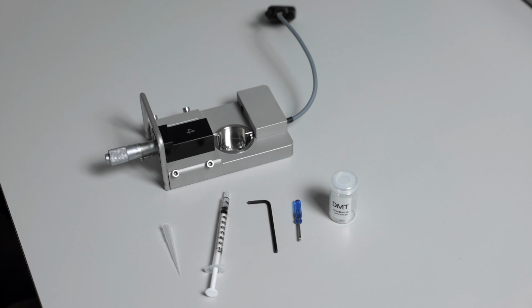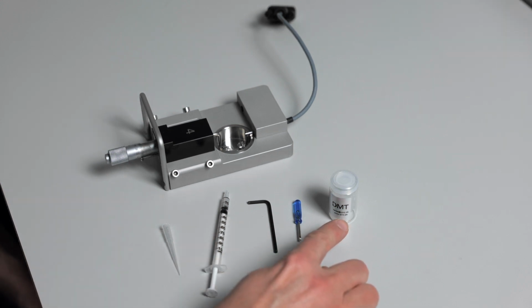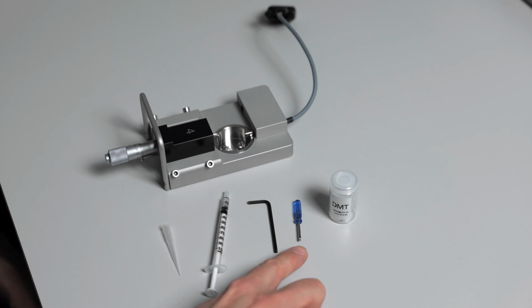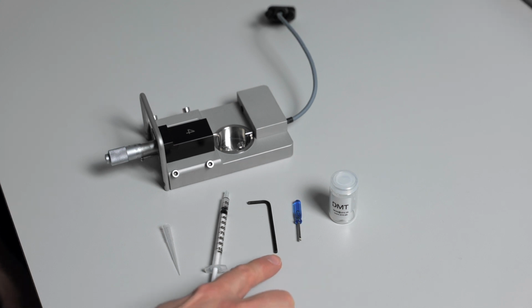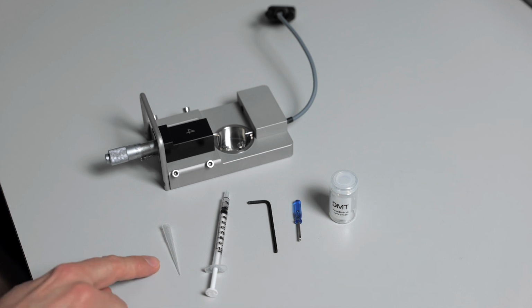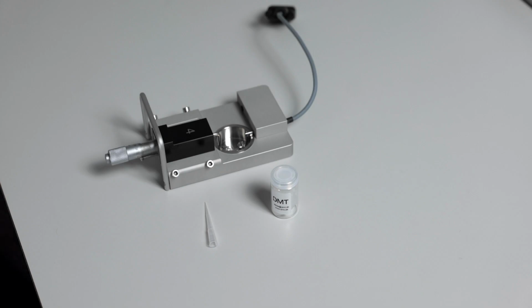To do this, you will need the silicone grease that came with your system, as well as the small screwdriver, the Allen key for removing the transducer housing, a 1 ml syringe, and a pipette tip. These will be used to apply the new grease. The first method is a quick and easy way to reapply the exterior grease that may have been removed during the cleaning process. If you are experiencing what we call transducer drift or unstable force readings, then you may want to do the more involved method, which requires removing the transducer.